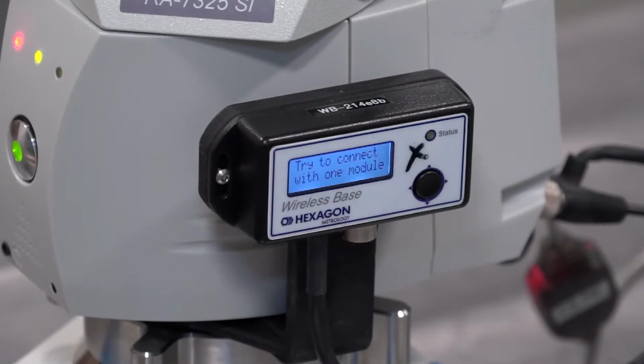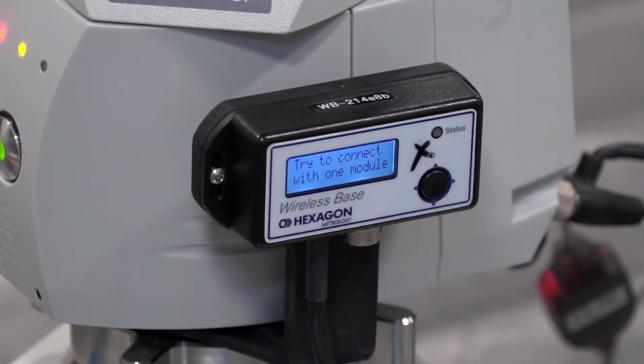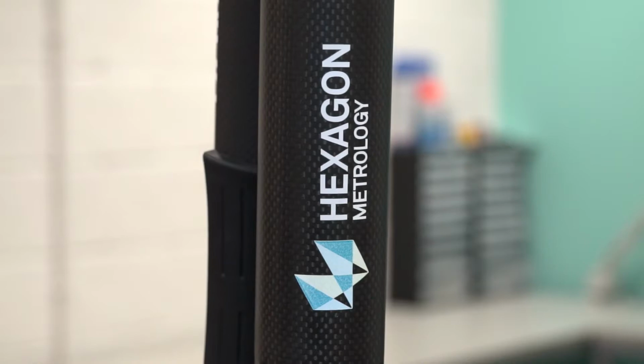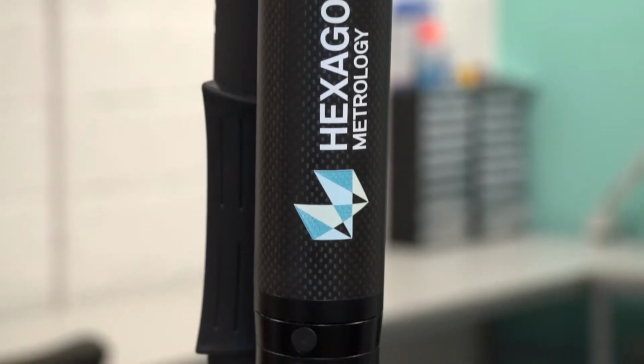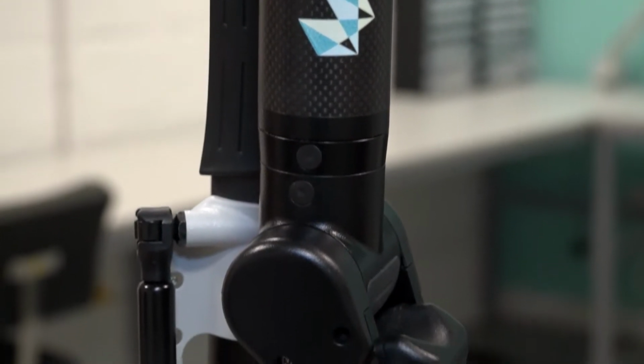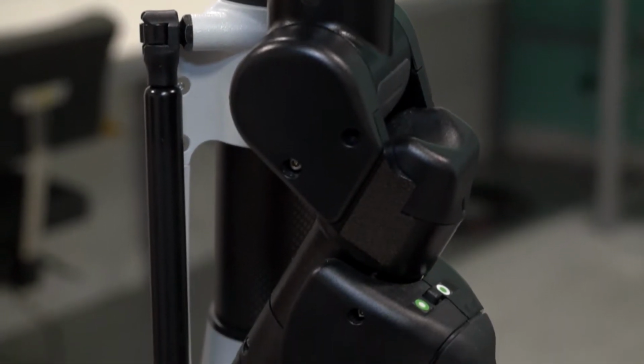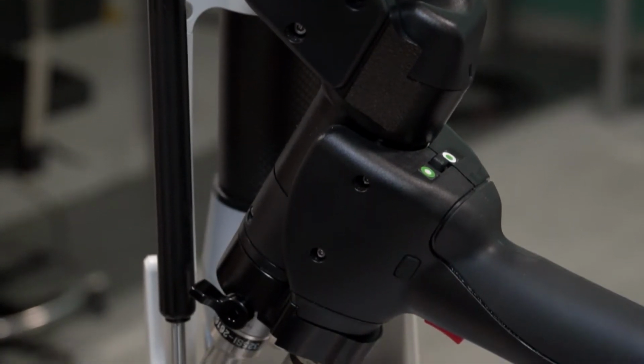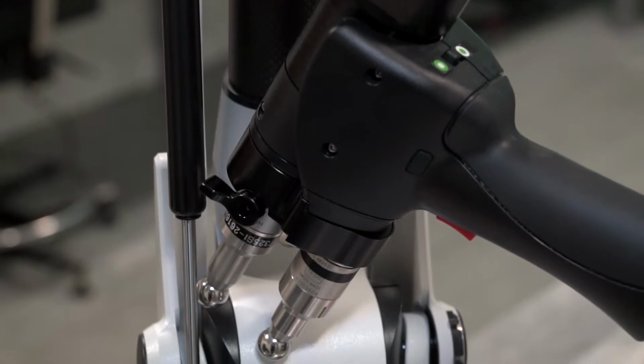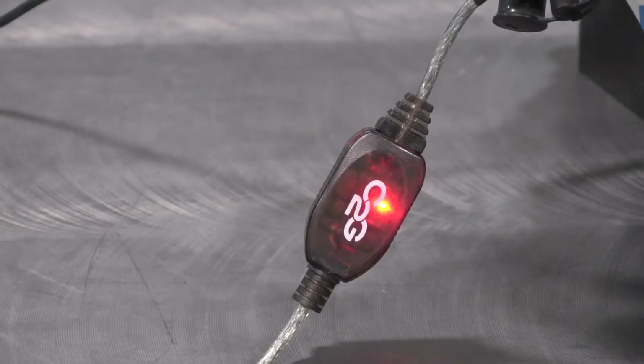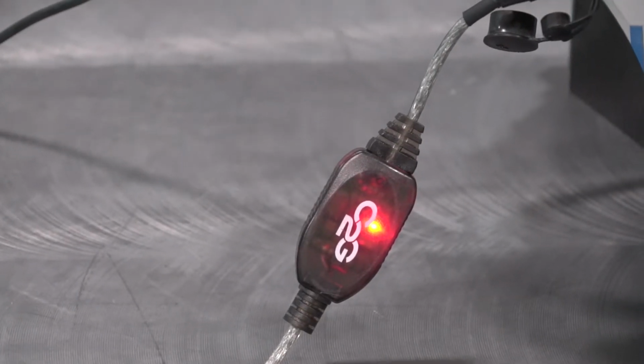We also have a temperature-controlled environment for the arms. The arms also have temperature sensors while we're doing the calibration to allow for the compensation to be a lot better. And once we've carried out the calibration, then we can go and do a B89 recertification, the same as what the factory do in France. We're the only people in the UK that can actually do this.